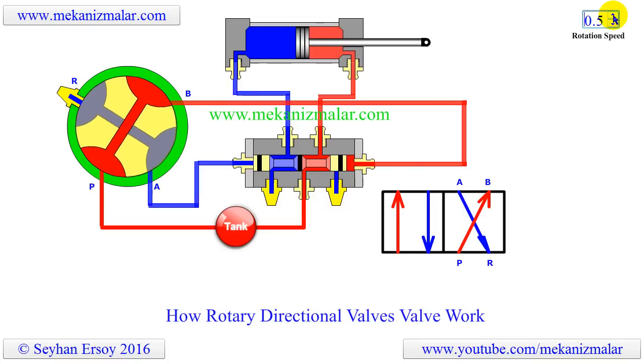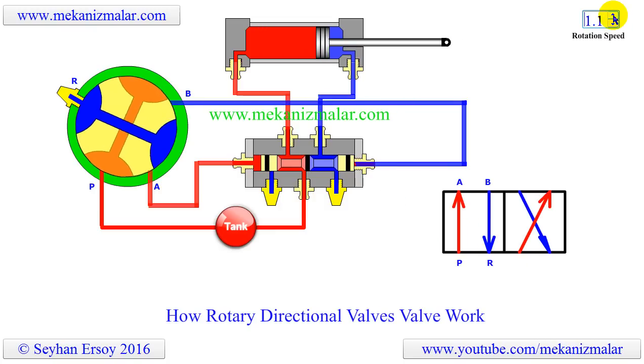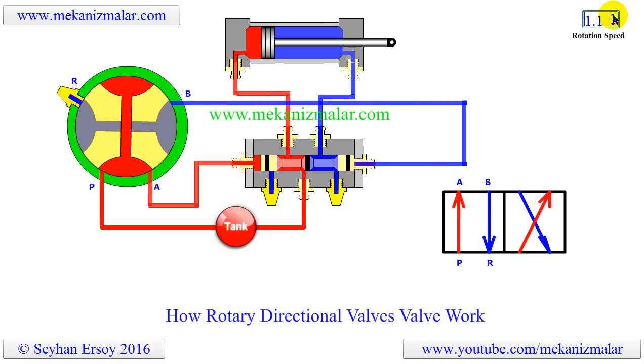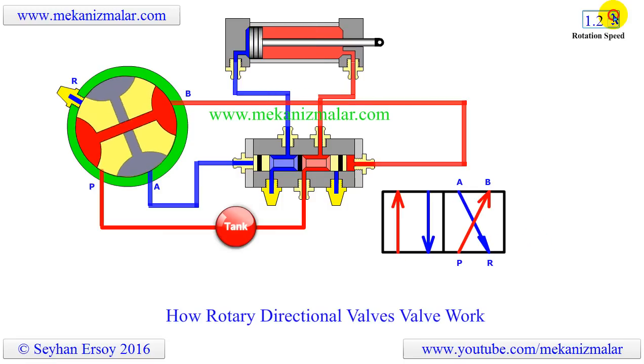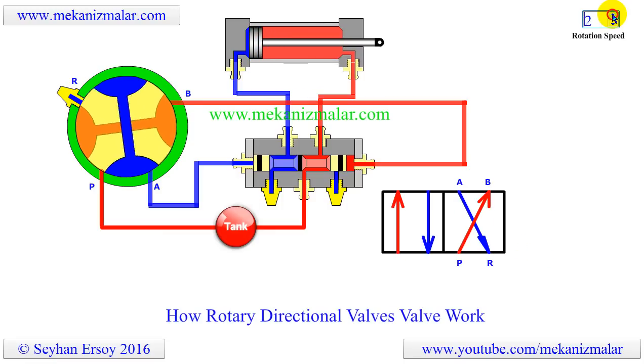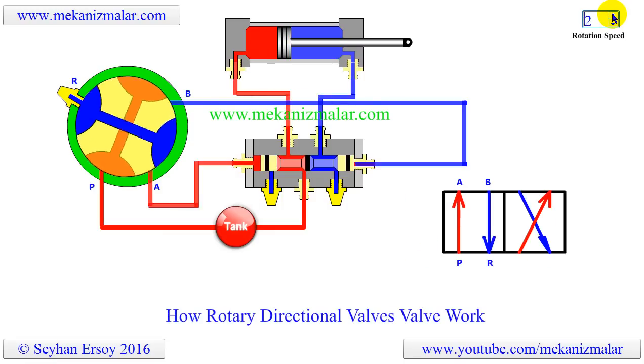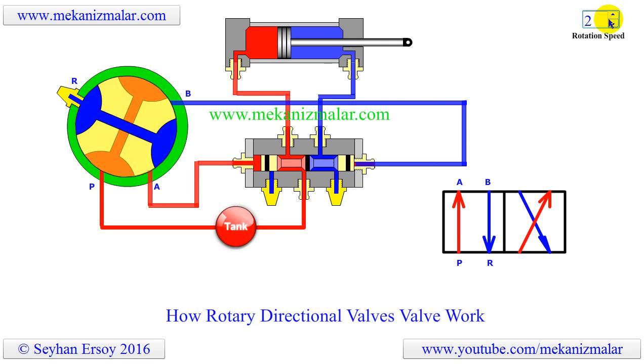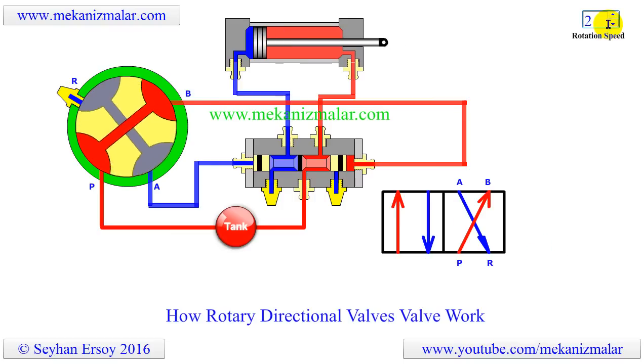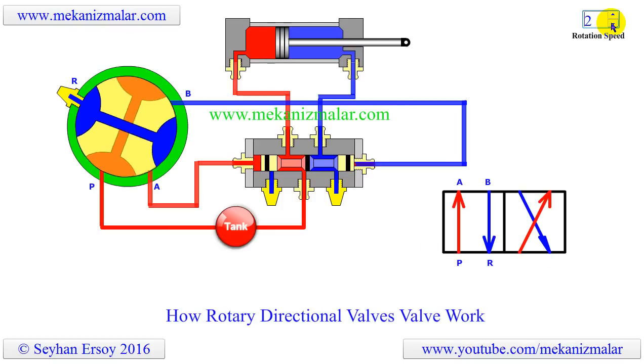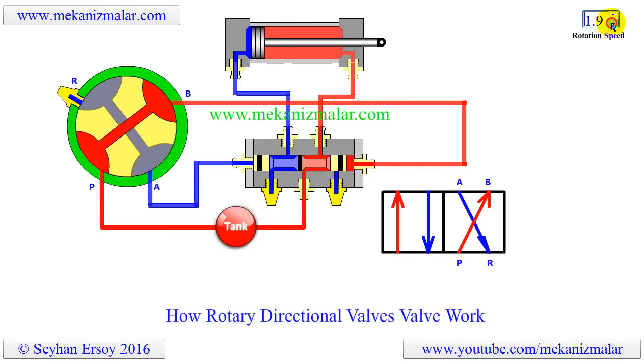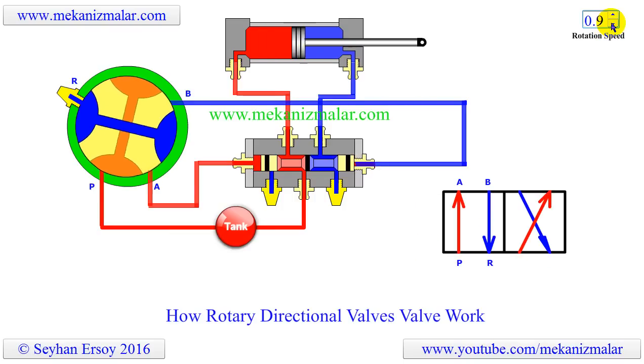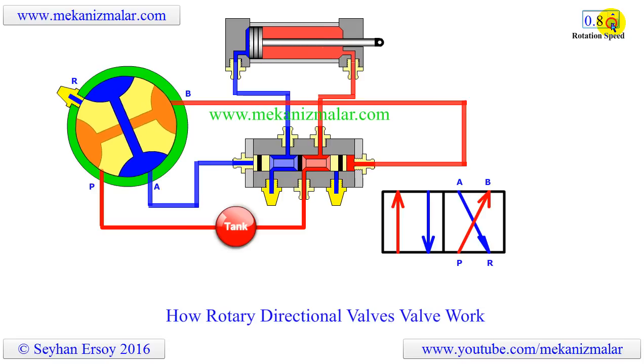Increasing the rotation speed of the rotary valve will cause the piston to reciprocate much faster. However, if we increase the rotation speed of the spool too much, the piston may not keep up with this pace of rotation. We may attach quick exhaust valves to the cylinder ports to release pressurized air in the cylinder much faster.